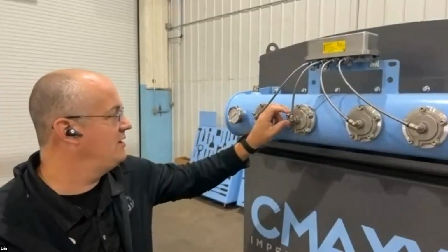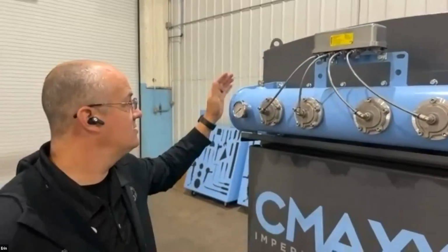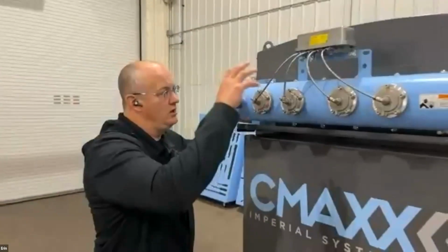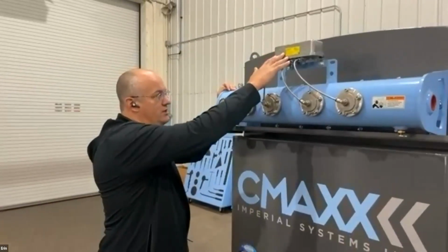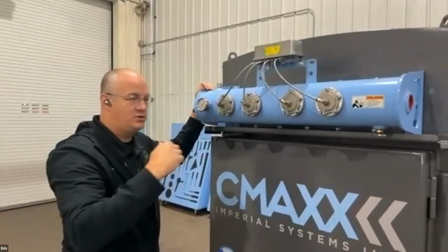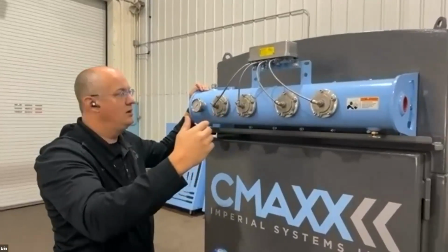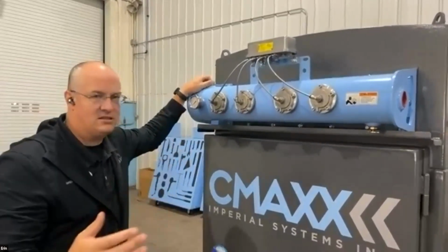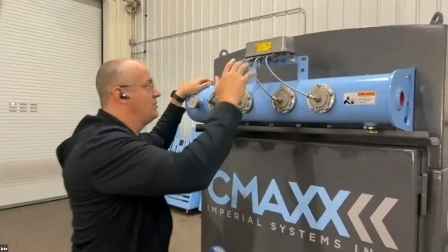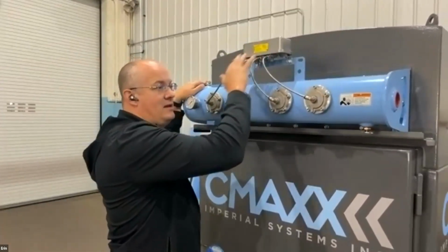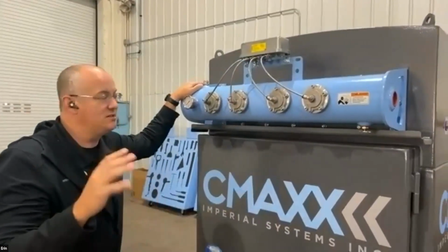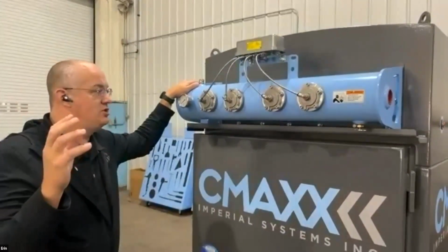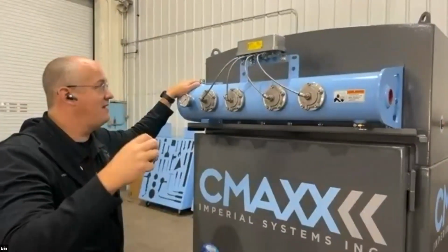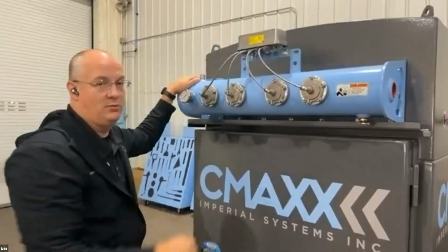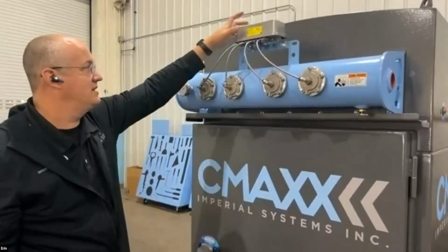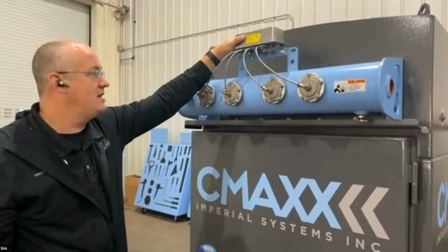We always recommend that you have clean, dry air coming into the compressor. So when you install this, if you're going to be in a colder climate, which most of you up there are, unless you're speccing something out in Florida, I would always recommend that as a great thing to add. It doesn't cost that much, but it saves a ton of wear and maintenance, having to climb up on a ladder to figure out what's going on here. It's a very simple device that's going to save a lot of headache in the wintertime.